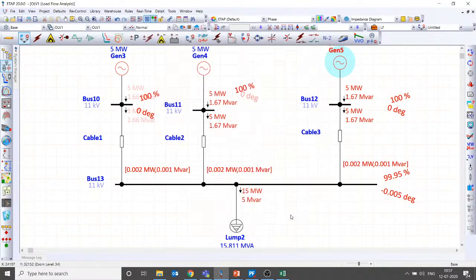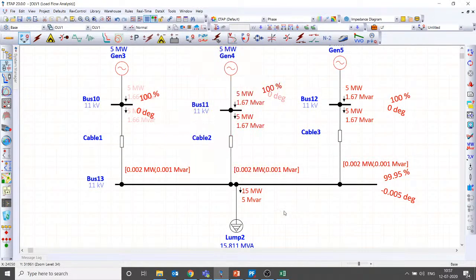Now what I have done is put all these generators in voltage control mode and run a load flow. I have given 15 megawatt and 5 MVAR, and I have given the cable lengths as equal, right? Let me display the cable lengths.